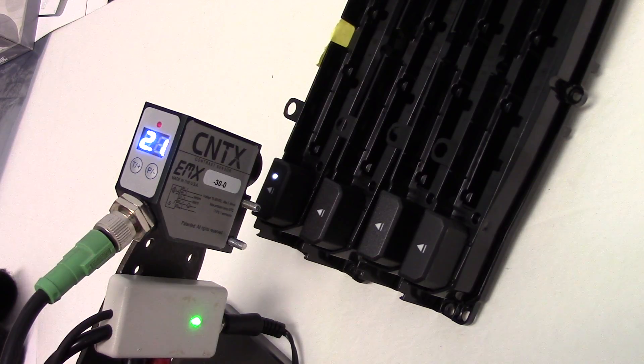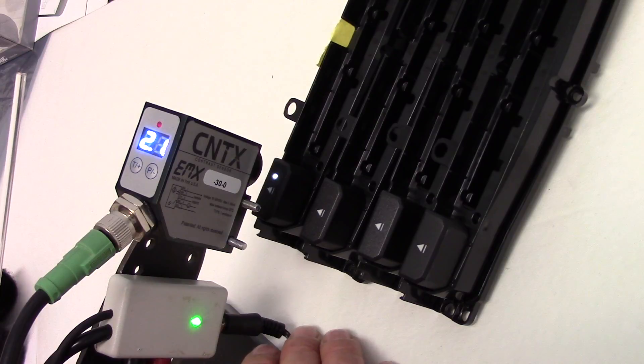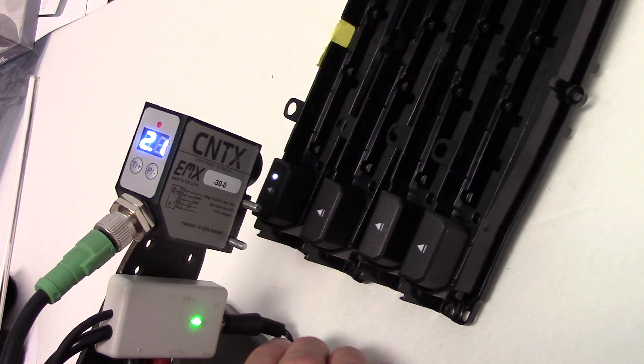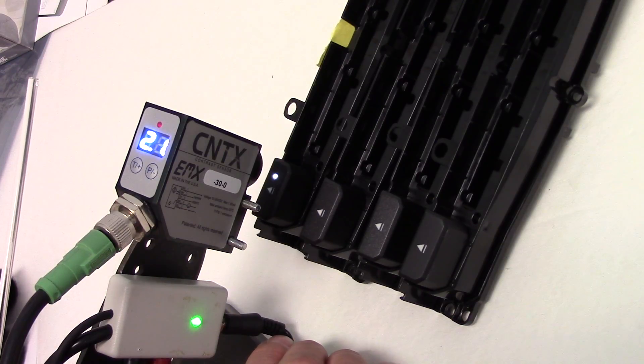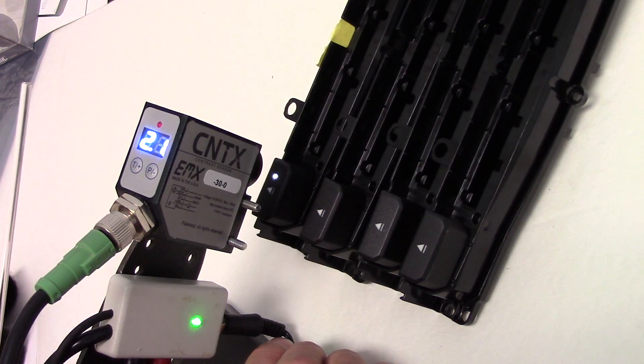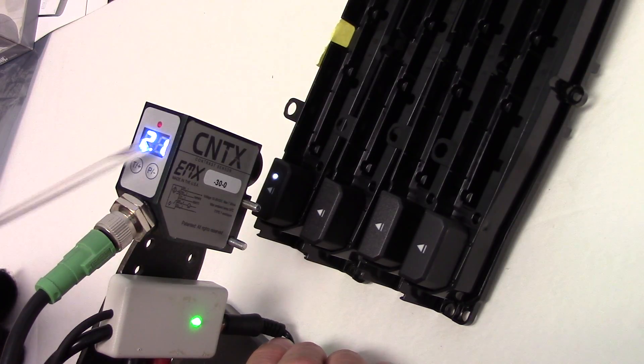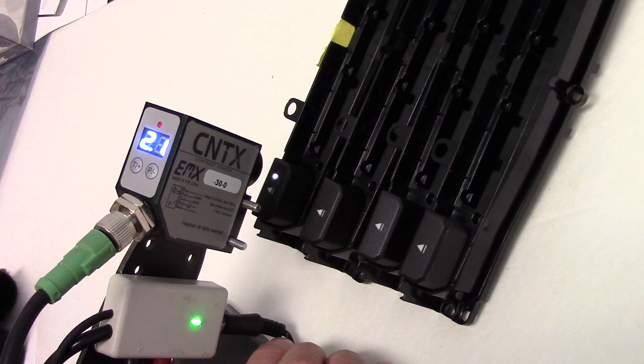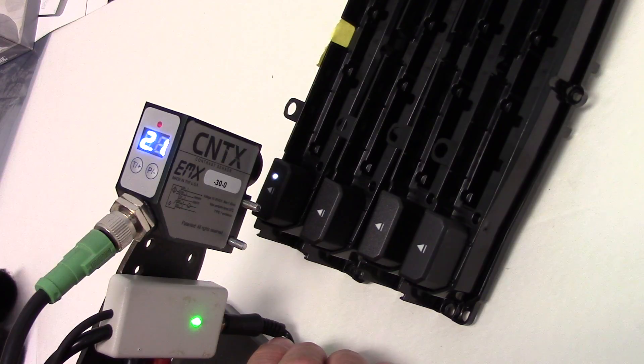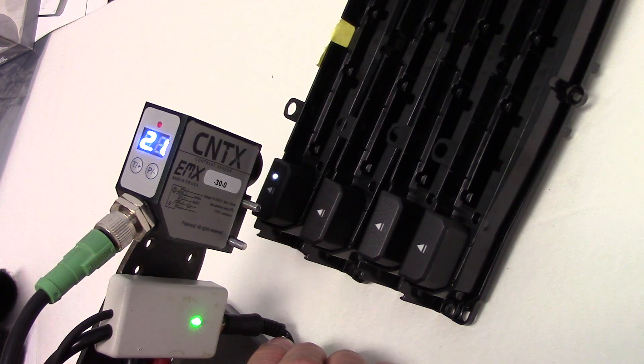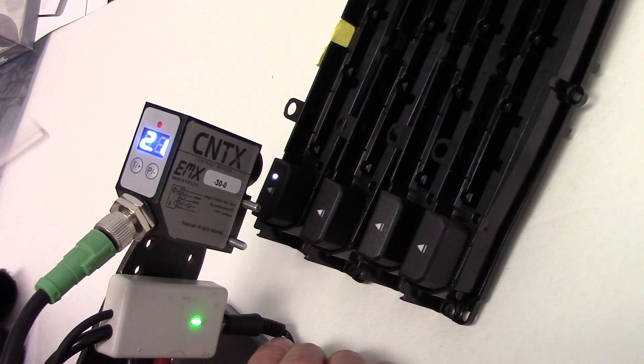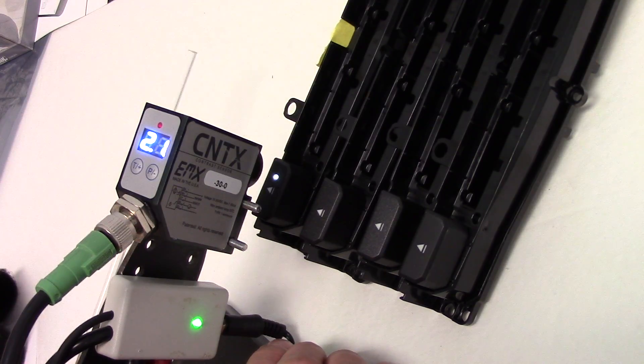We are going to read each one of these switches. The first one is metallic. It reads 21. The discrete output is set when the value exceeds 15. So right now the discrete output is on.